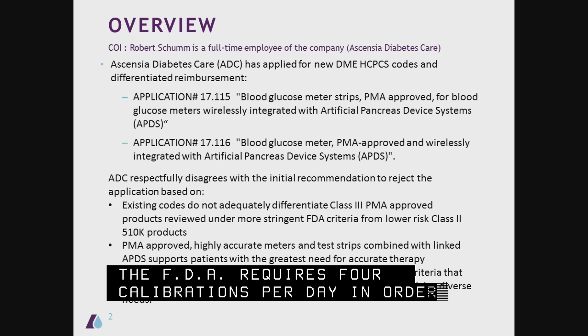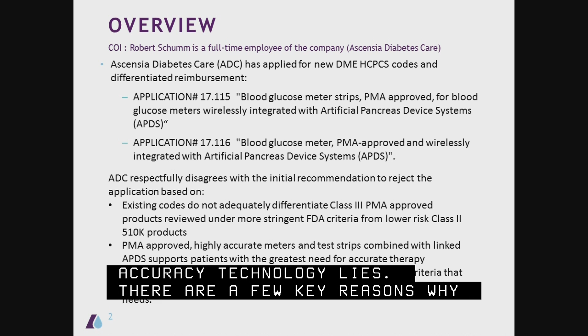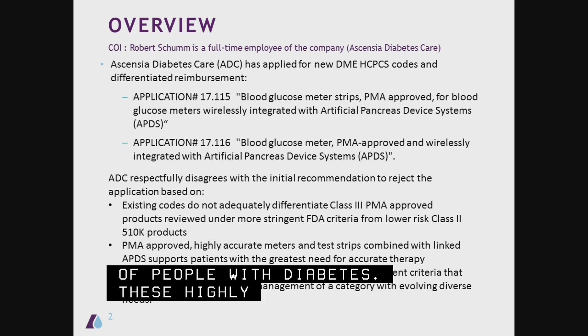Importantly, the strips are a key area here because that's where much of the technology lies. I know it seems like it's a lot in the meter, but those strips are very much where the accuracy technology lies. There are a few key reasons why the existing reimbursement codes for blood glucose monitoring do not provide patients the needed access for the artificial pancreas system, which I'll talk about here. First, the existing codes do not adequately differentiate between Class 3 PMA-approved products reviewed under more stringent criteria as part of the artificial pancreas system used by type 1 patients with diabetes, and the lower risk Class 2 products cleared under a 510K that are used by a broad range of people with diabetes. These highly accurate PMA-approved meters and strips are needed to support the optimal functioning of these innovative new systems for the patients with the greatest need for that accurate therapy.